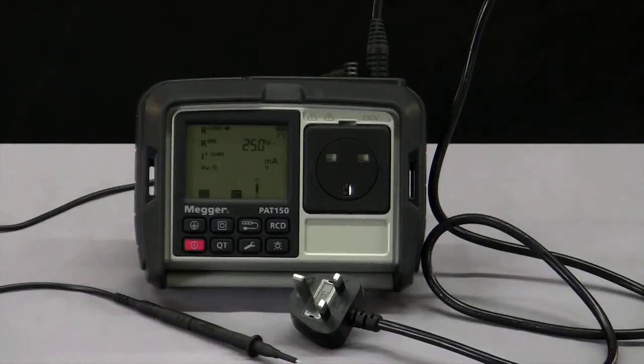The PAT150 allows you to test earth continuity of fixed appliances such as hand dryers without disconnecting them from the mains. Once you've connected your PAT150 to the supply and have your bond lead connected, you can access this facility in the quick test mode.